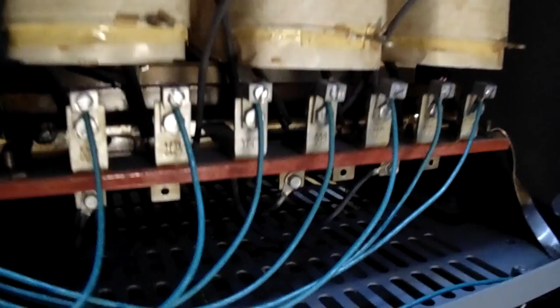So as you can see here, we have H2, X3, X0, H1, X2, H3, and X1. That is how those correlate. So your X's are the low side. That is why there's 4 of them. X0 is your neutral. X1, 2, and 3 are your lines of that star configuration.